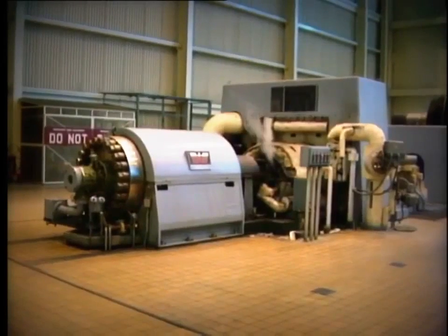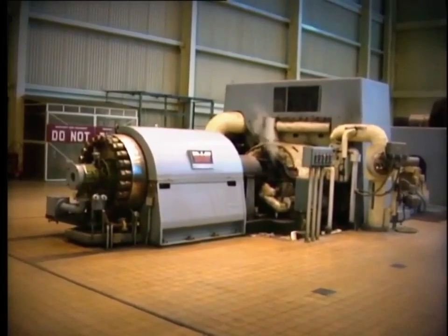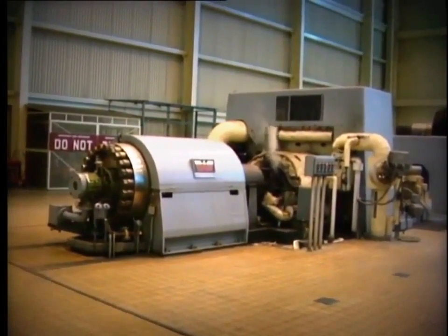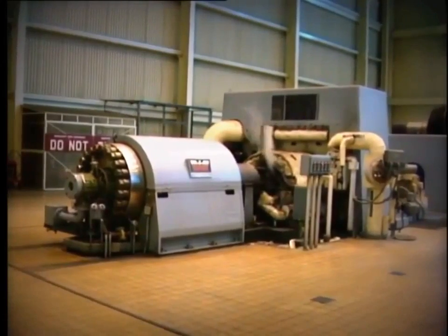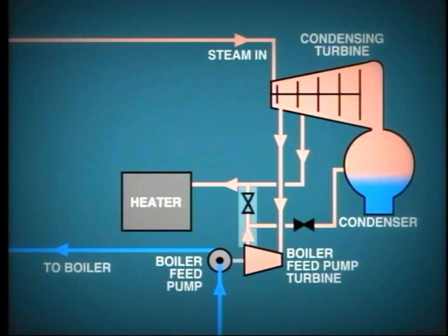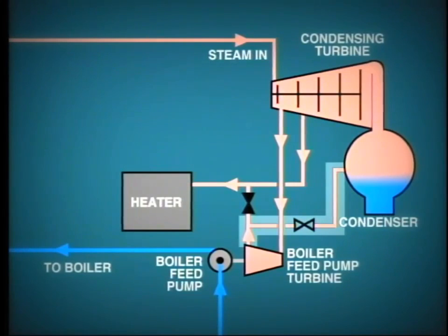On large turbine generator units, the feedwater pumps are sometimes driven by steam turbines using extraction steam or cold reheat steam. The discharge from the turbine drive may then be piped to a lower point of extraction for further heat utilization. Alternatively, it may be piped to the condenser so that the condensate may be recovered even if the latent heat is lost to the cooling water.